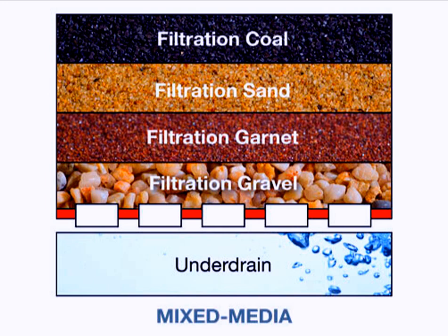Grain size has important effects on the efficiency of filtration and on backwashing requirements. Proper size is determined by sieve analysis that uses the American Society for Testing and Materials ASTM standard test C136, most recent edition.